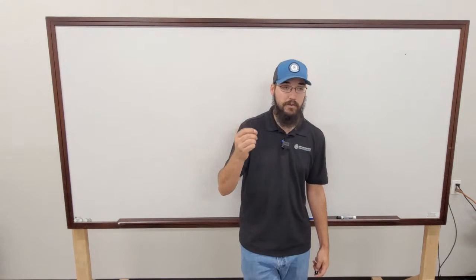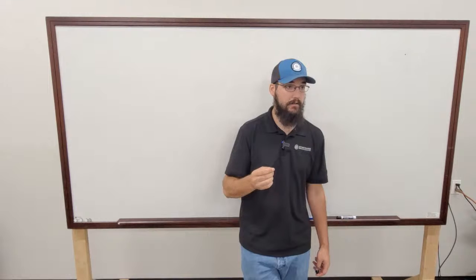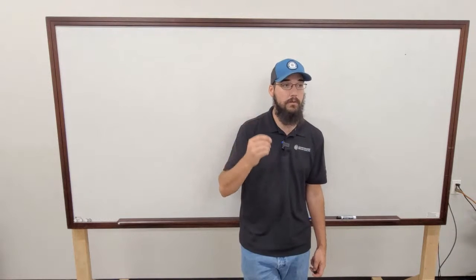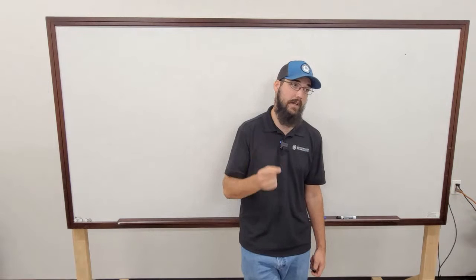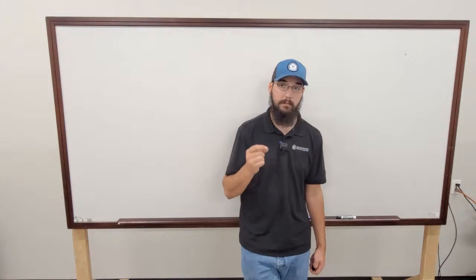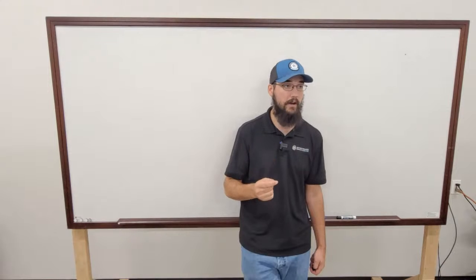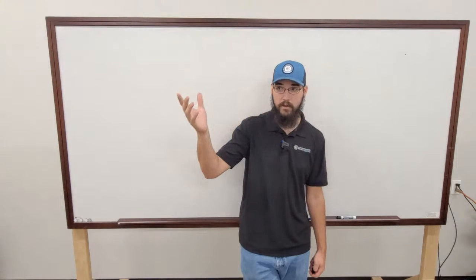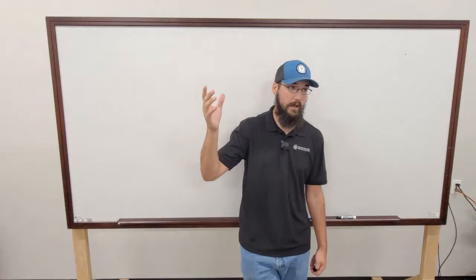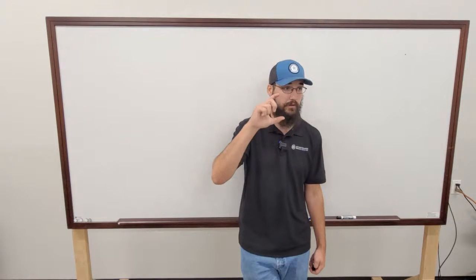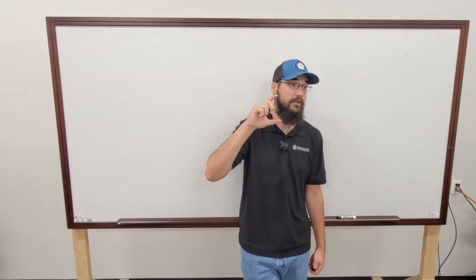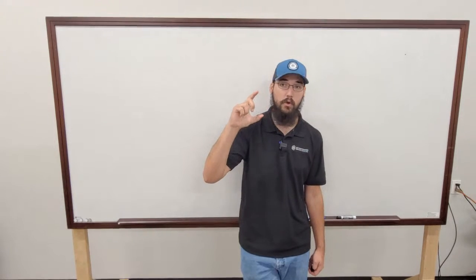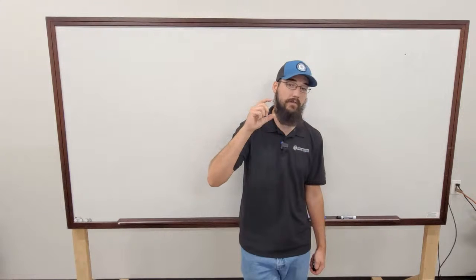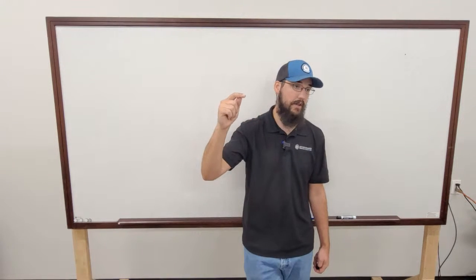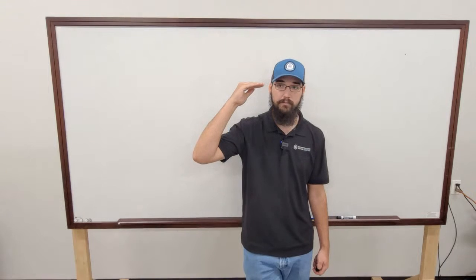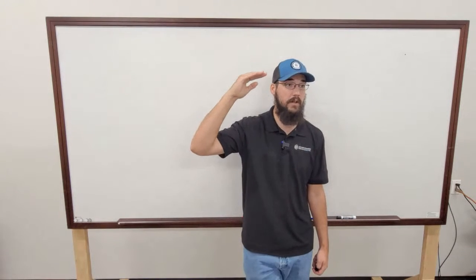EXVs on these machines don't have feedback. The machine doesn't actually know the real position. Whatever that display is telling you is calculated, and it's based off of a time. It's a floating point valve. So just like we talk about floating point actuators, the EXVs function on the same principles. They're just a timed valve, and that chiller knows that it takes 90 seconds to fully open or fully close. And based off of how many pulses it gives, it knows that it should be at 500 steps at X position.